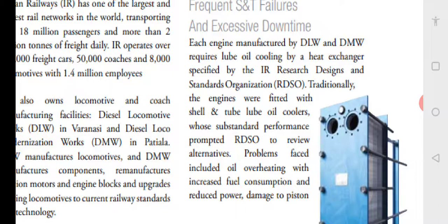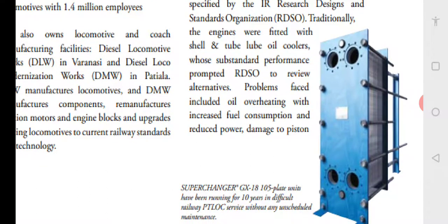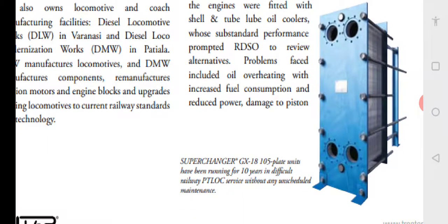Traditionally, engines were fitted with shell and tube oil heat exchangers whose substandard performance prompted RDSO to review alternatives. Problems included oil overheating with increased fuel consumption, reduced power, and damage to pistons. If lube oil temperature increases due to low cooling efficiency, the viscosity of the oil reduces, friction increases, power is reduced, and to compensate, higher fuel consumption occurs — also leading to piston damage.